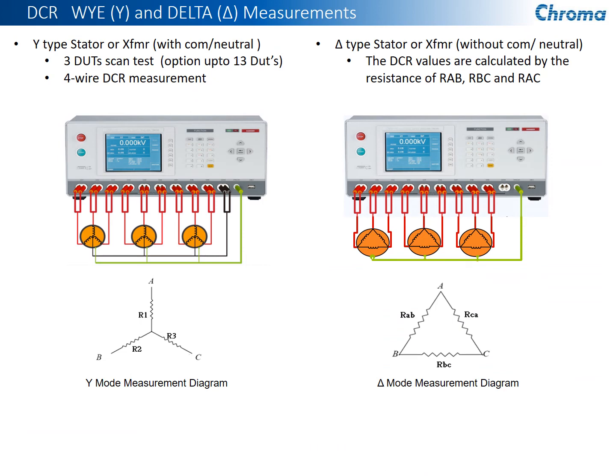Another test that we do for DC resistance measurement is referred to as delta and Y measurements. When you're looking at a 3-phase device, a 3-phase motor or 3-phase transformer, often the windings may be terminated or configured either in a Y configuration or a delta configuration. And as you can see in the resistors and the drawings showing below, that is an indication of how those windings might be terminated. In a Y configuration, all 3 windings have a common termination that may be used as a neutral, or if it's not used and it's only a 3-wire measurement of those 3 windings, normally you would get 2 winding resistances combined when you make that measurement.